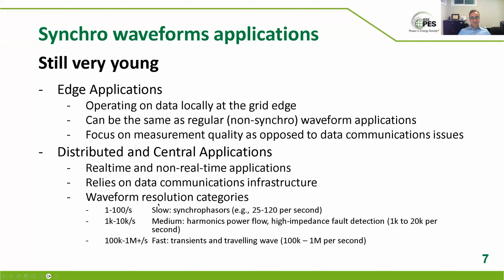In terms of waveform resolution, or sampling rate speed if you like, I want to define 3 categories. One that we call basically slow, which is like synchrophasors. You get 1 every cycle or 2 every cycle, that sort of level. That almost doesn't fall into the waveform; it's in the phasor domain. It's just 1 or 2 measurements per cycle. It's not enough to really describe a waveform unless it's purely, nicely sinusoidal.